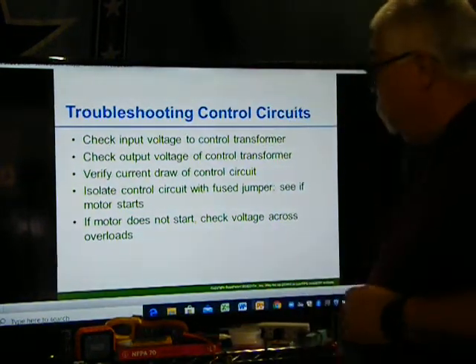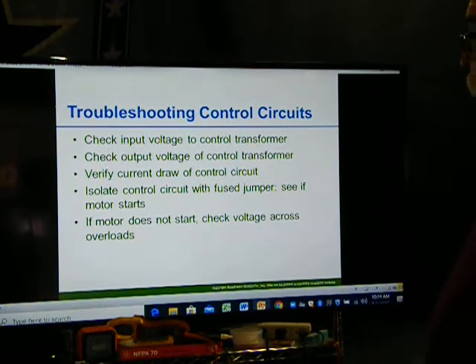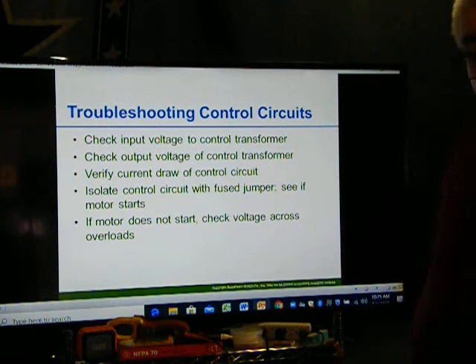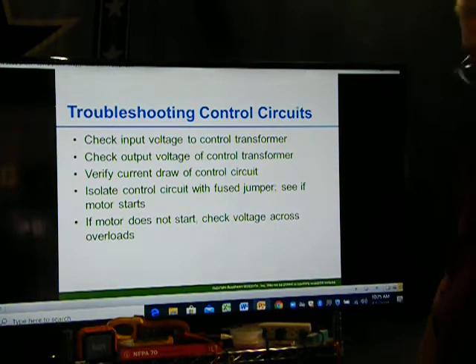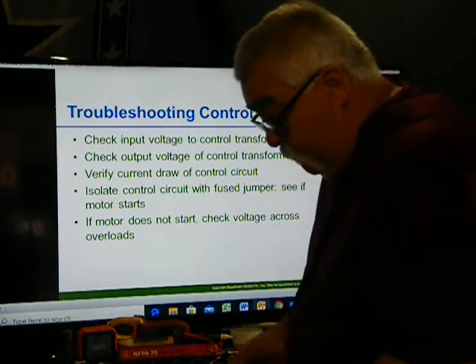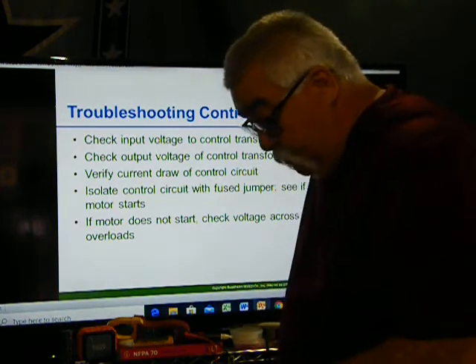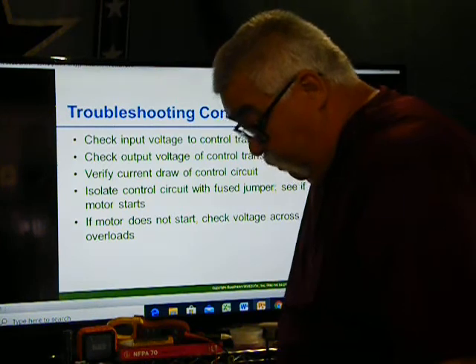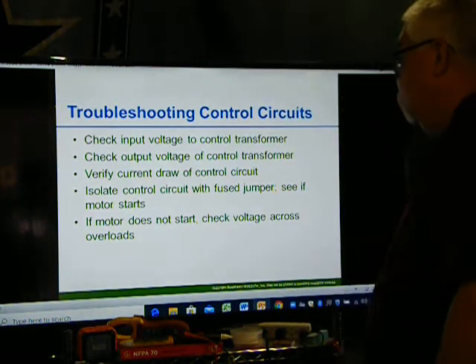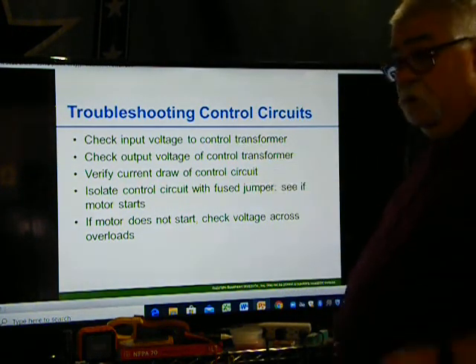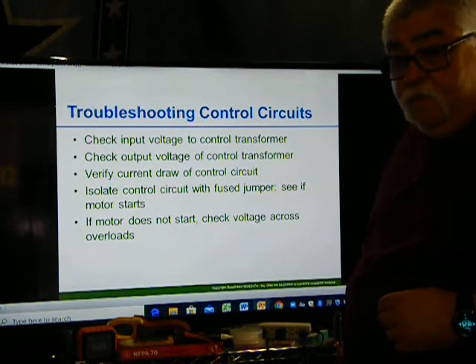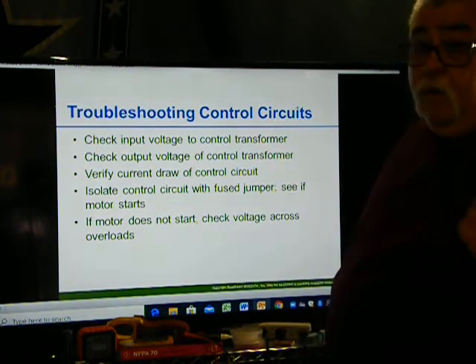It says troubleshooting a control circuit. Okay, step 1. Check to see if you got voltage at the transformer, or if you have your control circuit coming off a breaker somewhere. It says a control circuit may be the source of the trouble. Follow the steps illustrated. Check input voltage of the control transformer. Make sure you got power coming in. Make sure you got power going out.